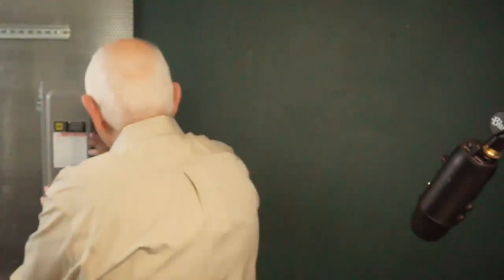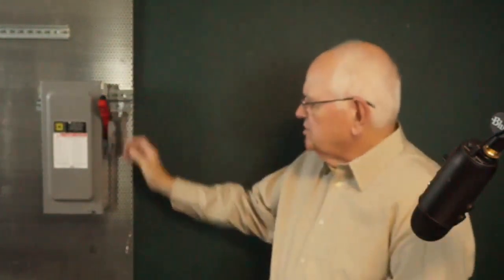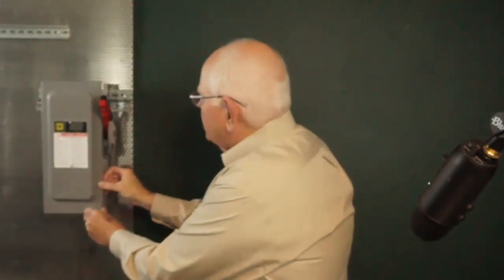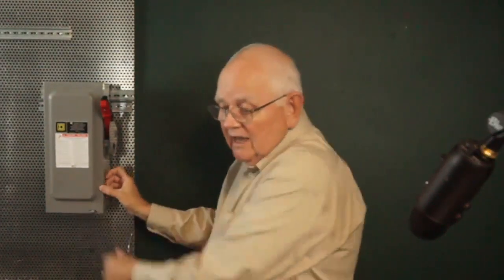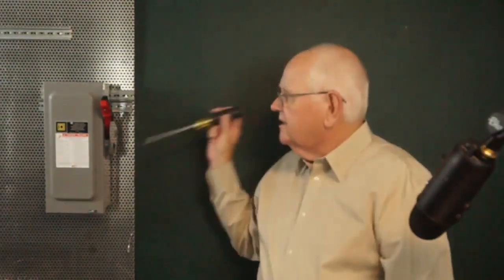Now, let's talk about the protection from electrical hazards. First of all, 50 volts and greater. That's always our key, isn't it? 50 volts and greater must be guarded against contact, and that can be either by the insulation or obviously the enclosure itself. Now, we have interlocks that prevent opening the door, except for qualified persons. So if my disconnect is in the on position and I try to open this door right now, I can't do it. It's interlocked, right? I have to override the interlock. If I'm a qualified person, I can do that.